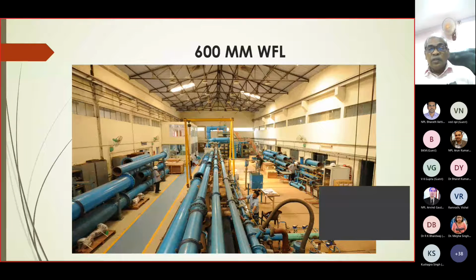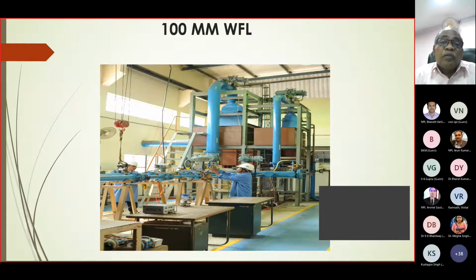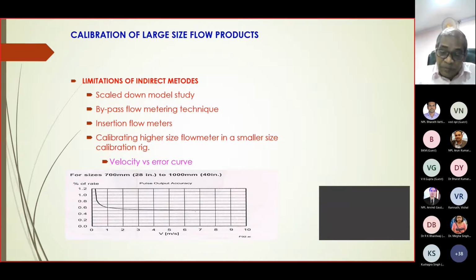See, in this water flow lab, after a few years, we were receiving many quotations for calibrating small flow meters, even from NAL, HAL, ISRO, some 15 mm turbine flow meter like that. Using this big lab for that is very uneconomical. So later on, we developed another lab called the 100 mm water flow lab. Whatever flow meters or valves come at 100 mm or less, we shift to this lab. And the accuracy and everything else is comparable to the earlier one.